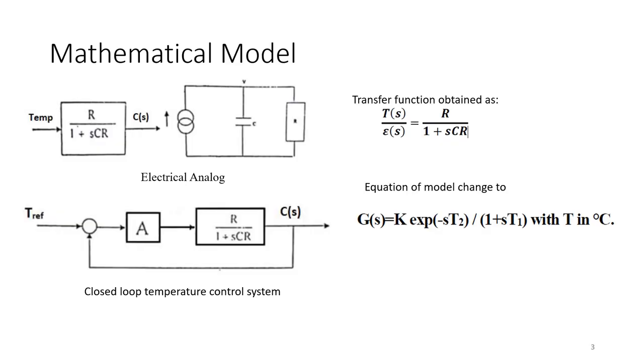Moving on to the mathematical model — the first step in the analysis of any control system is to derive the mathematical model. We obtain the transfer function as T(s)/ε(f) = R / (1 + sτ), which is a first-order type-0 system. Such a system should be easily controlled in closed-loop. The input is in the form of heat and the output is the final temperature. Since the output is obtained only after a delay, the model changes to G(s) = K·e^(−sT2) / (1 + sT1), where T1 is the time constant and T2 is the delay.